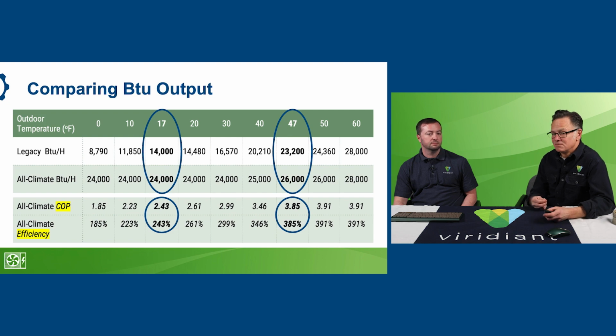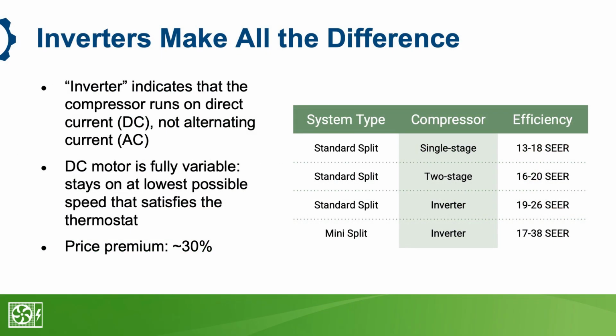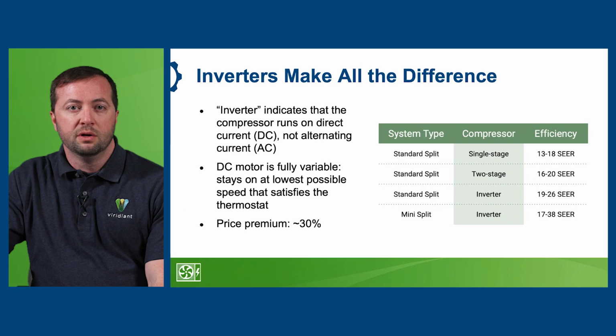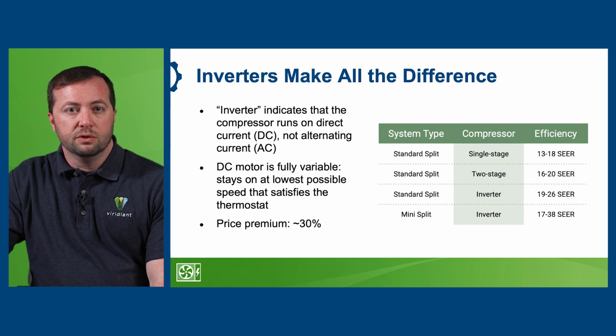Inverters are the reason that heat pumps have become much more efficient and lead to greater comfort. An inverter runs on DC instead of AC. These DC motors are fully variable or modulating, meaning they can adjust based on the current heating or cooling needs of the home. When there's lower demand, they run more slowly, using less energy. Legacy systems are single-stage AC motors that can only be either on or off and don't modulate. Two-stage systems are able to run at either a low stage or a high stage.